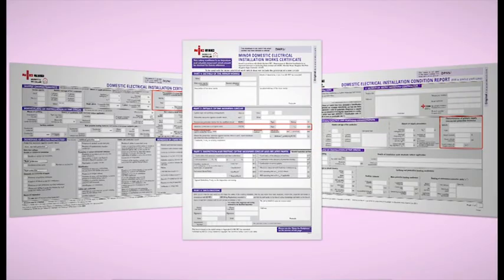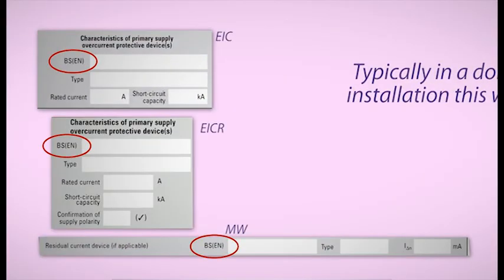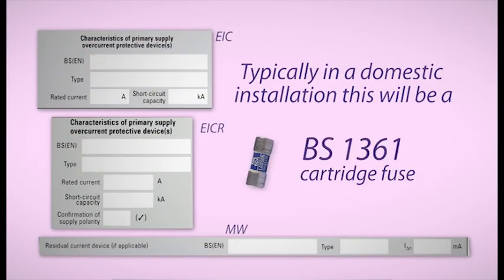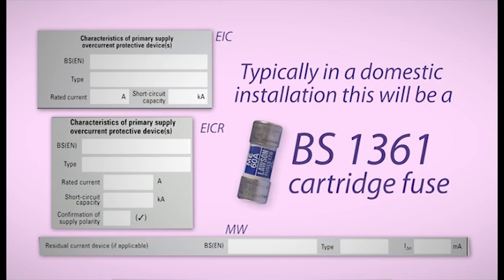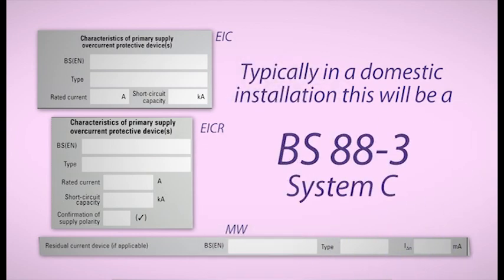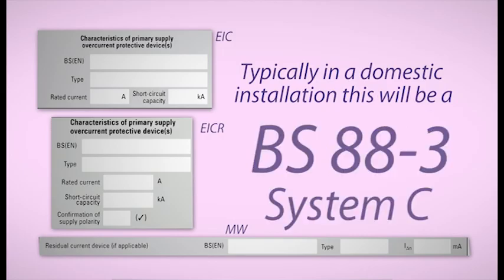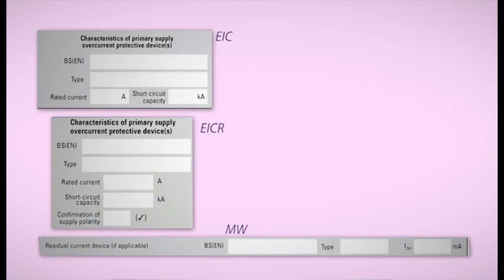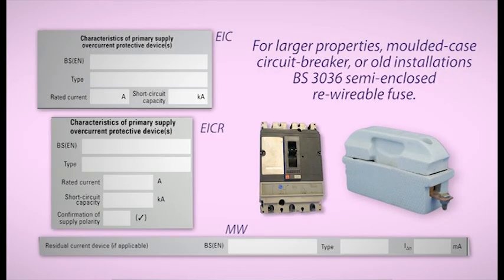Let's look now at the characteristics of the primary supply overcurrent protective device. The first box requires the BS EN number for the device. Typically, in a domestic installation, this will be either a BS 1361 cartridge fuse or a BS 88-3 fuse System C, which was introduced with Amendment number 1. For larger installations, you might find a moulded case circuit breaker, or in very old installations, a BS 3036 semi-enclosed rewirable fuse.